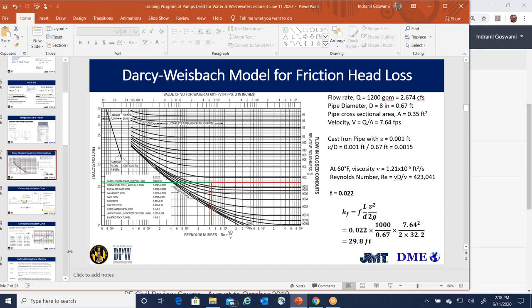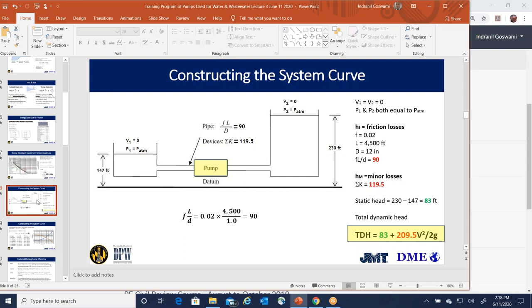In a two-reservoir system, if the pump were not present, flow would naturally go from the higher reservoir to the lower one by gravity. To force flow from left to right, the pump must overcome the static head difference. In our example, reservoir one is at 147 feet and reservoir two is at 230 feet, giving 83 feet of static head to overcome.